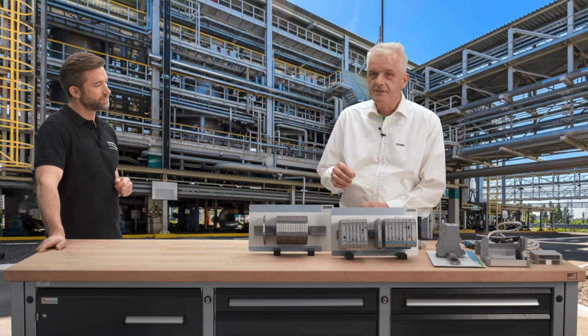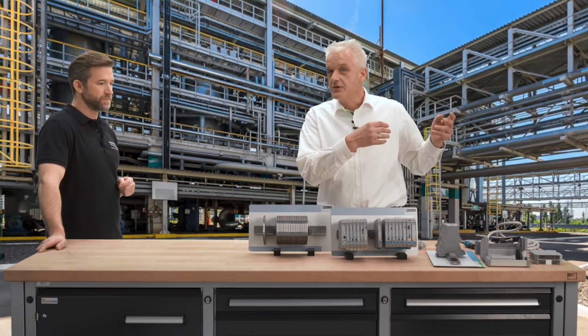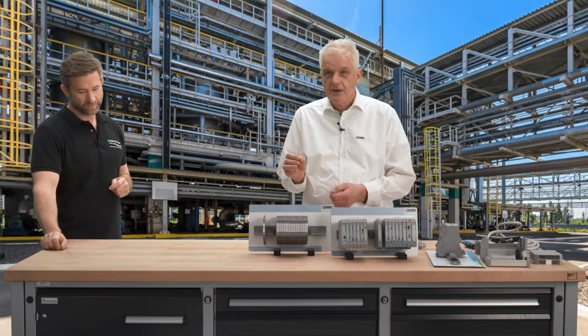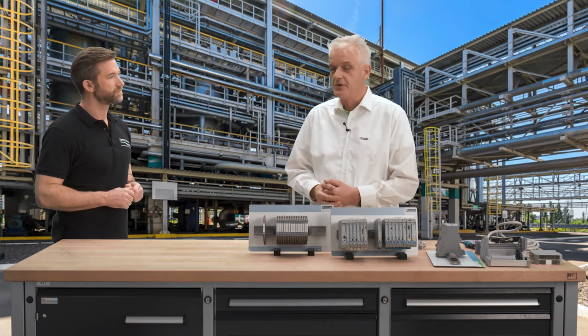The principle here is, simply put, the safe limitation of the spark energy, for example, in the event of a short circuit, to a non-ignitable level. But unlike all other types of ignition protection, it does not only refer to the field device, but to the Ex i field device and the associated equipment, which represents the interface to the non-intrinsically safe circuit. For example, the analog in-output card of the control system, and ensures on the Ex i side that the energy conducted into the field is not ignitable.